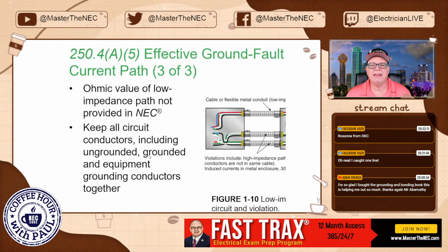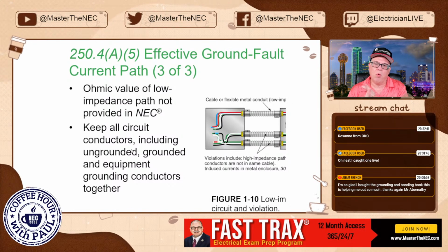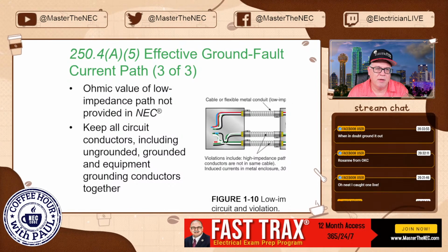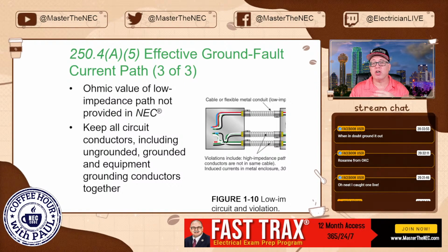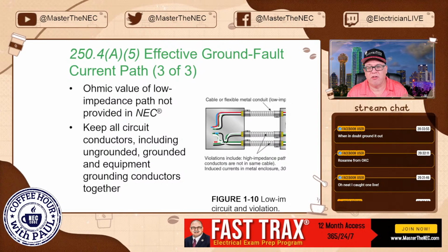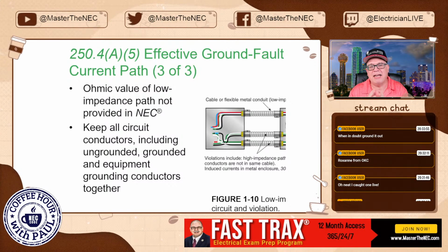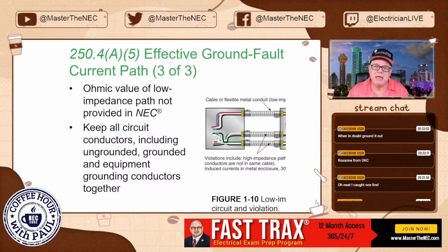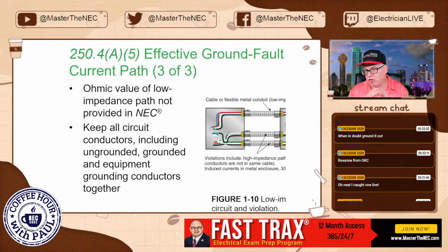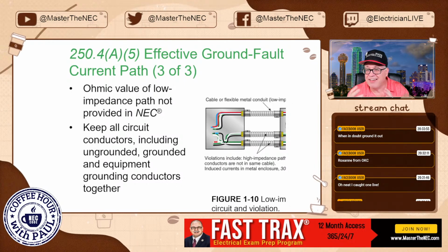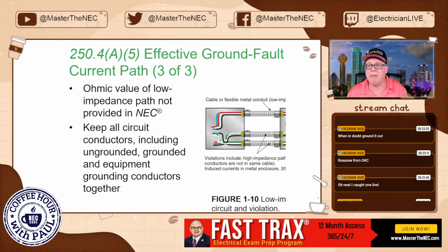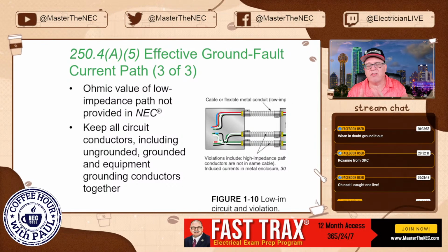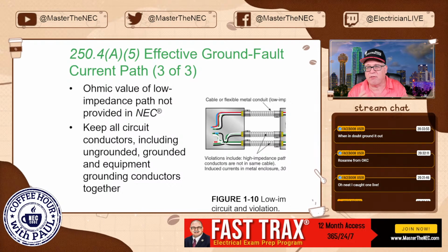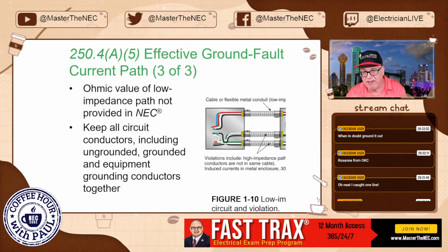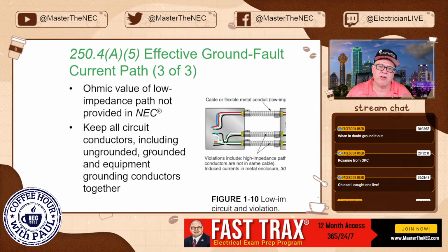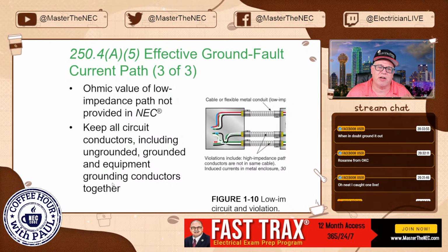Now, one thing you have to remember is that what also affects impedance is how you run your conductors, how you run your circuits, not separating them out so you create an expanding, collapsing magnetic field. It creates high impedance when the conductors of a circuit aren't all run together. This can actually create counter EMF, and it can keep these conductors from being a low impedance effective ground fault current path due to that effect. So keep all circuit conductors, including ungrounded, grounded, and equipment ground conductors together.